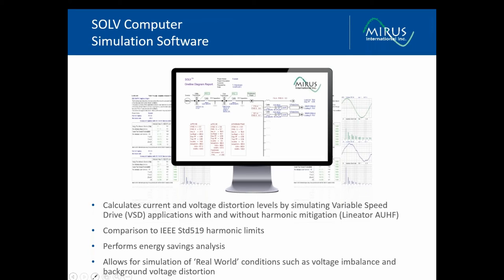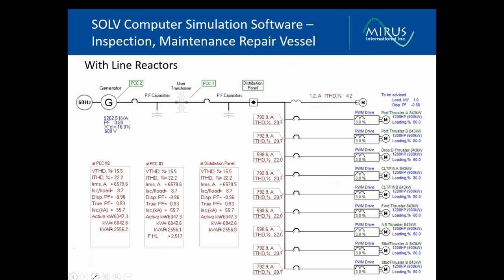There's a lot of information that can be generated as you run your simulations. It has the unique application of allowing the voltage imbalance and background voltage distortion to be included in the analysis. There's no other harmonic analysis software in the world, even if you're spending tens of thousands of dollars on the software, that allows this particular feature. And it's very critical when you're looking at the various harmonic mitigation solutions and applications.